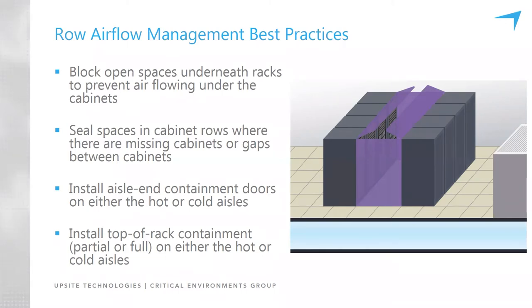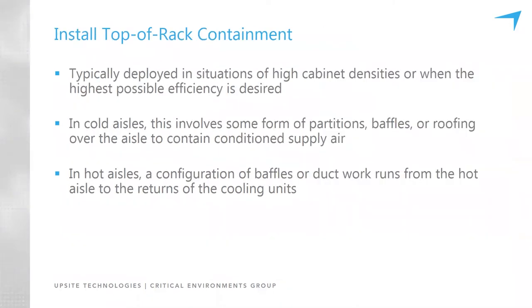Lastly, the fourth best practice is top-of-rack containment. Hot aisle containment typically features an above-rack barrier around the perimeter of the hot aisle, extending upward from the racks to the ceiling — or vice versa, from the ceiling down to the tops of the racks. Cold aisle containment can involve a roof, a capped aisle, or even a partially capped aisle spanning the cold aisle. Installing containment above the cabinets is typically done for higher-density environments.